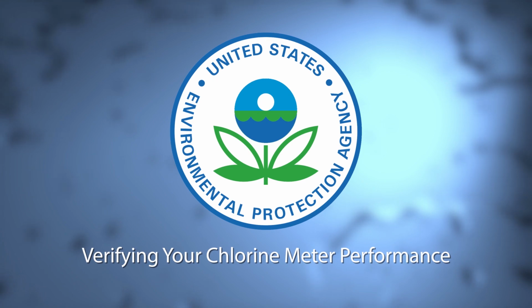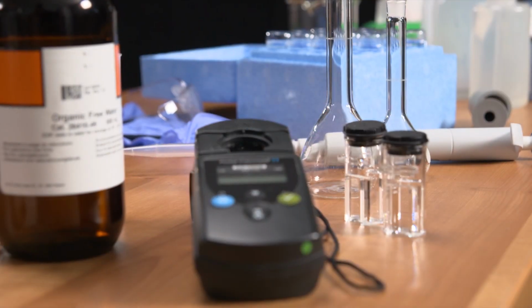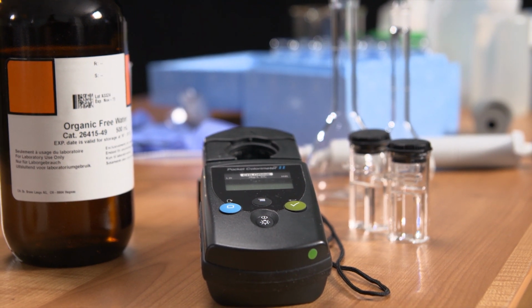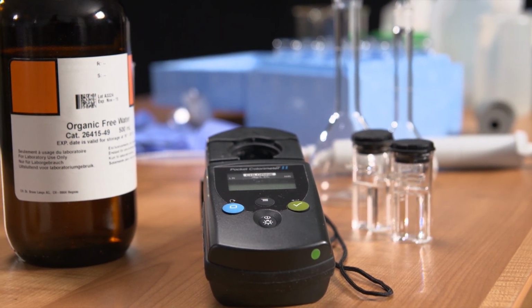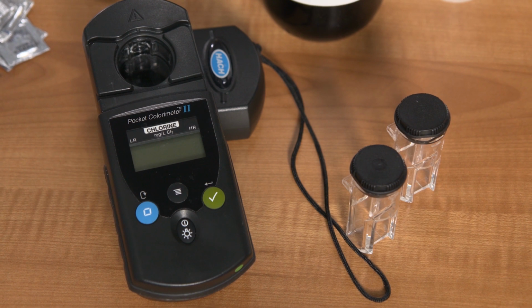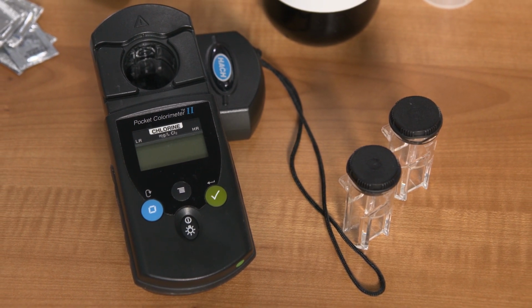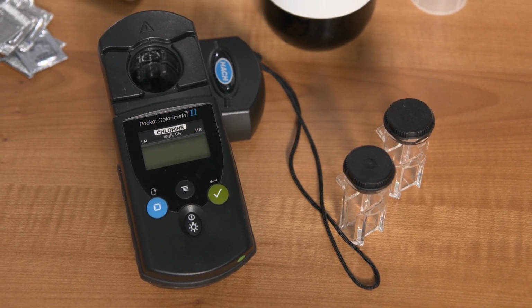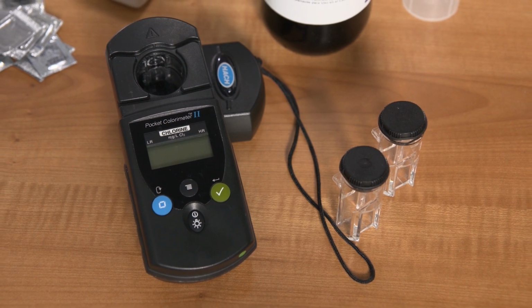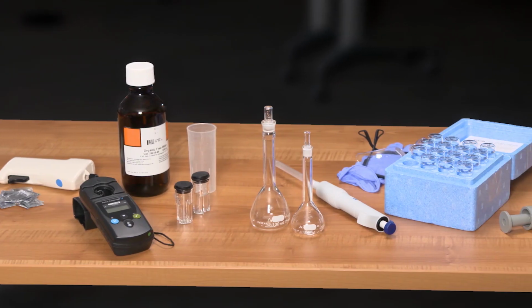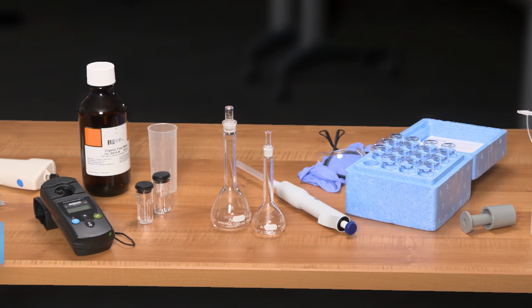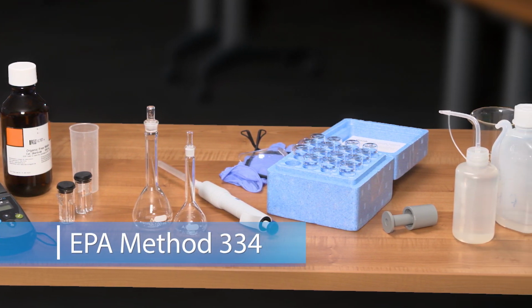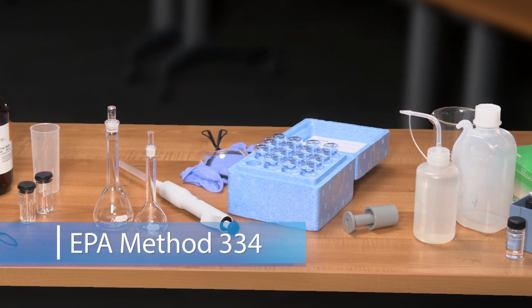This instructional video will explain the procedures for checking to make sure that measurements of grab samples of chlorine residual are performed accurately. This video can apply to both portable and benchtop instruments. Additional steps are required for calibration verification of continuous chlorine measurements, and these steps are not included in this video. Please refer to EPA Method 334 for continuous chlorine calibration verification.